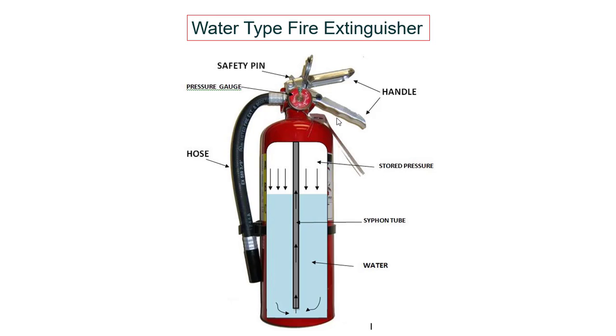Water type is most suitable for Class A fire — solid fire — for example wood, paper, and charcoal. This is a portable type, usually coming in 9-litre capacity. The outer container is filled with water, while the inside has compressed air at the required pressure. When you squeeze, through the siphon the pressurized water will go and extinguish the fire.